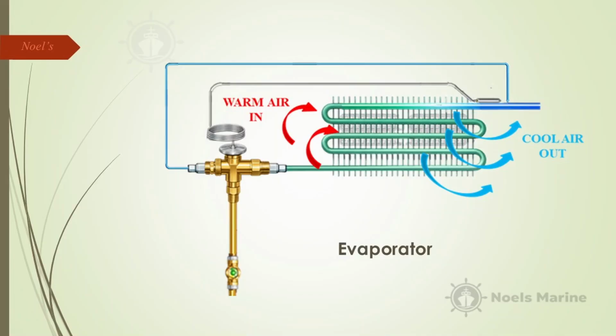Step 1, the evaporator. Or as I like to call it, the heat sponge. The heat sponge, I like that. So physically, this is just a big box with a fan and a coil, right? Usually tucked away somewhere. But thermodynamically, this is where the magic happens. Warm, humid air from your cabins blows over this coil. Right. And inside that coil is low pressure, very cold refrigerant. As it absorbs the heat from that cabin air, it actually starts boiling. Boiling, but it's cold. Yes, because pressure and temperature are linked. At that very low pressure, the refrigerant boils at a very low temperature. So as it boils, it turns into a gas, soaking up massive amounts of heat.